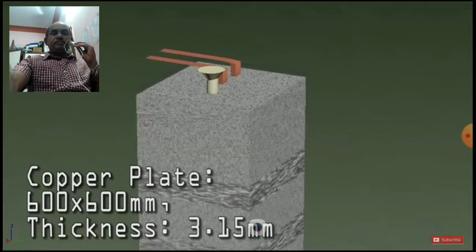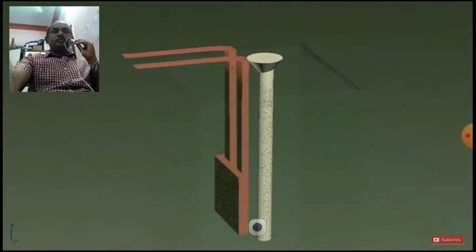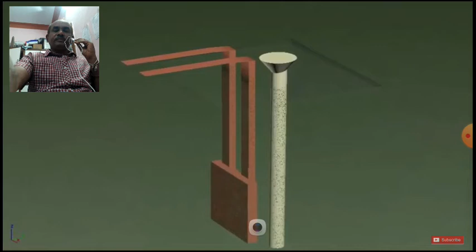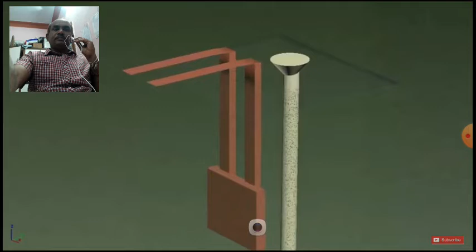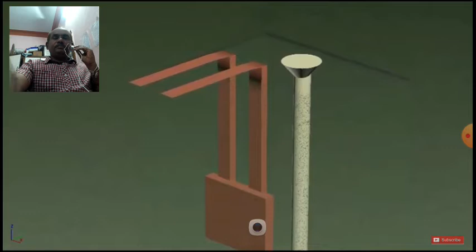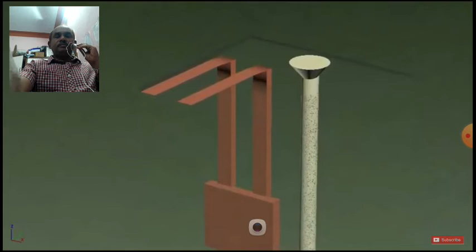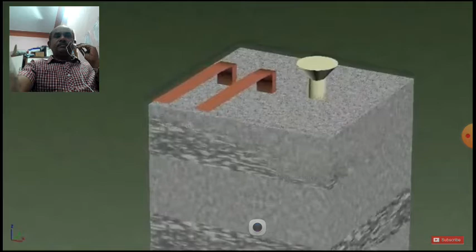Inside the salt and charcoal layers, a copper plate of size 600 mm by 600 mm and thickness 3.15 mm is positioned in the middle of the layers of salt and charcoal. Three GI strips of size 550 mm by 6 mm are fixed to this copper plate as shown. These strips should preferably be welded to the copper plate. A GI pipe of size 25 mm diameter is attached at the top with a funnel for pouring water inside the earth pit. This keeps the surrounding area near the earth plate moisturized.